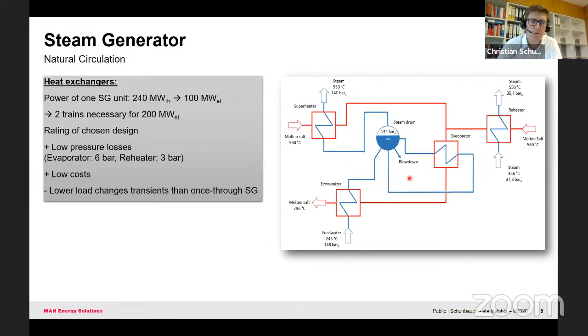Also here we discussed a lot of variants, and the focus was of course on cost optimization and on OPEX. In comparison to a once-through system, the advantage is that we have a lower pressure drop. The evaporator system has around 6 bar and the reheater 3 bar. We have lower cost. The disadvantage, so to say, is that in comparison to a once-through system, this system has a lower transient capability: we can drive 5 Kelvin per minute, whereas a once-through system can go 10 to 20 Kelvin per minute. But the decision was that it makes more sense because we know when we want to produce, and so we can take the time in advance.